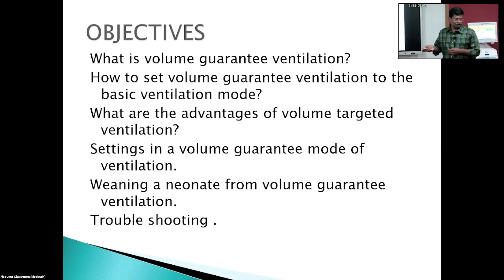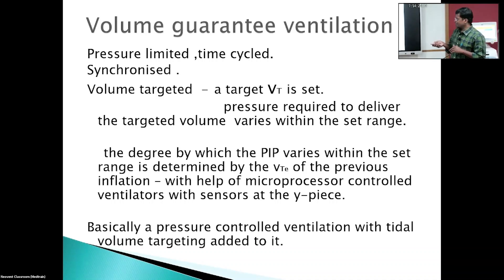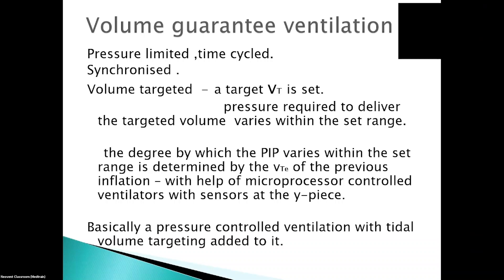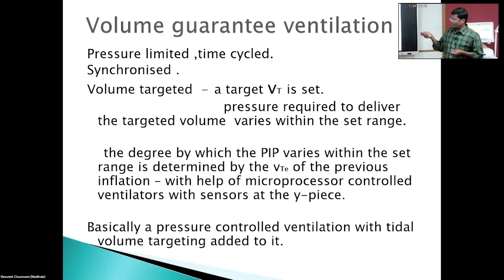Volume guarantee ventilation is nothing but pressure-limited, time-cycled ventilation. We set the peak inspiratory pressure, and it is time-cycled into expiration. The synchronized modes such as SIMV, ACMV, SIPPV, and PSV are the synchronized modes, and with these as a basic mode, we add volume targeting to it.